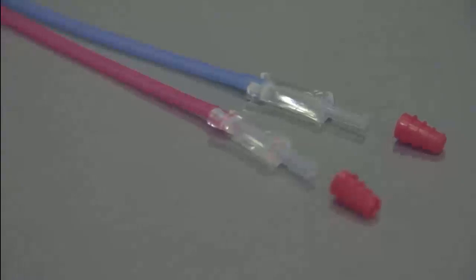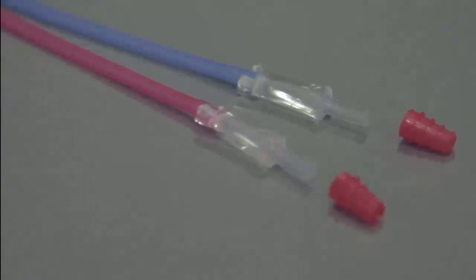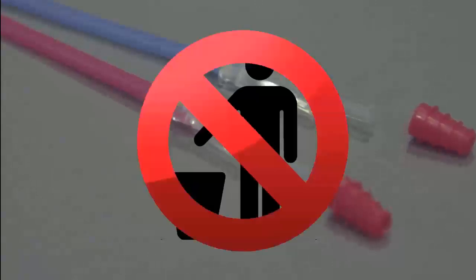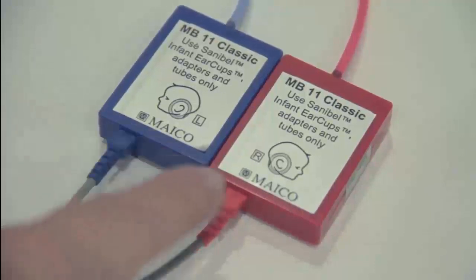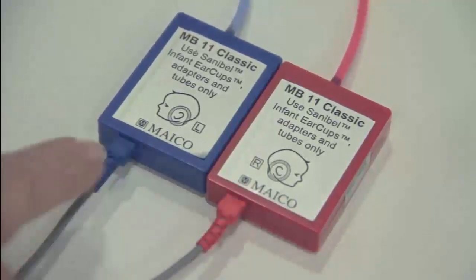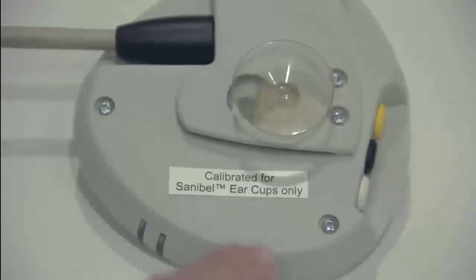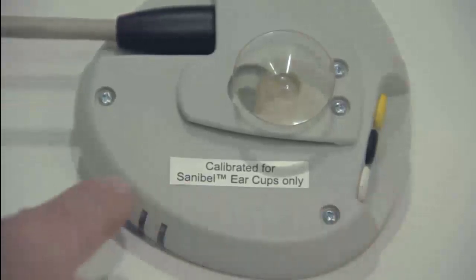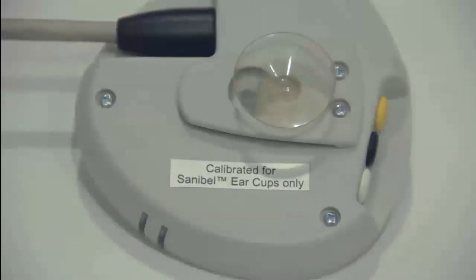Both are intended for single patient use and should be thrown away after use. The special adapters at the end of the red and the blue tubes that connect to the ear cups or the ear tips are not disposable. Be sure not to throw these away accidentally. The selection of ear cups or ear tips must be made at the time you purchase the MB11 Classic. The calibration of your hardware will be specific to your selection.